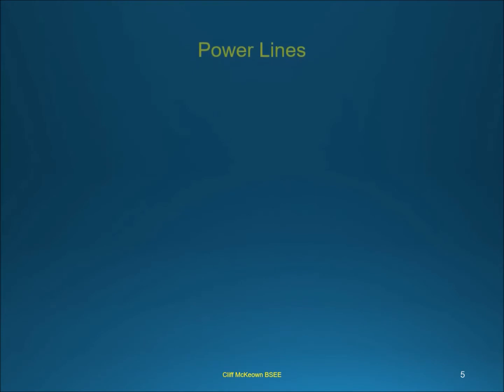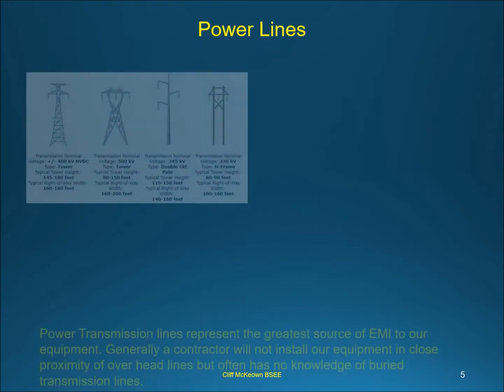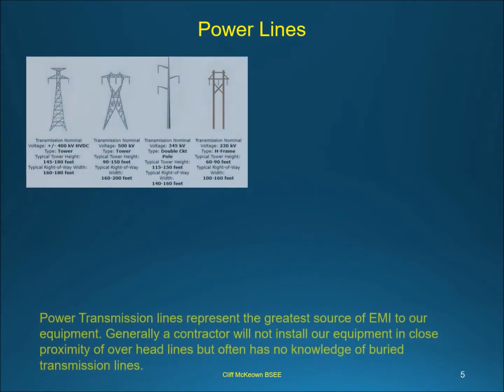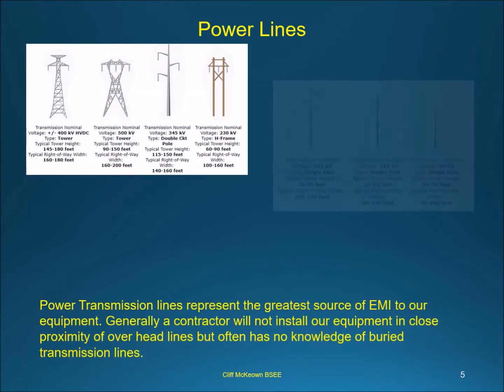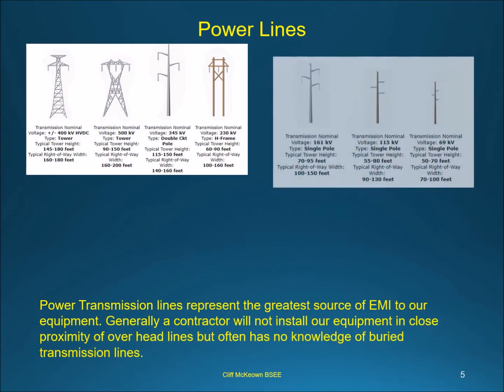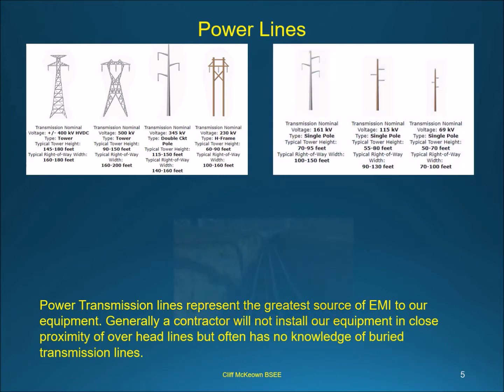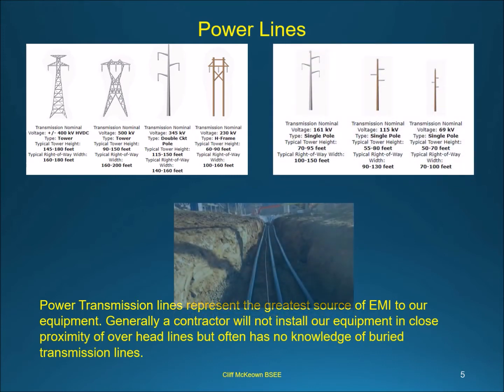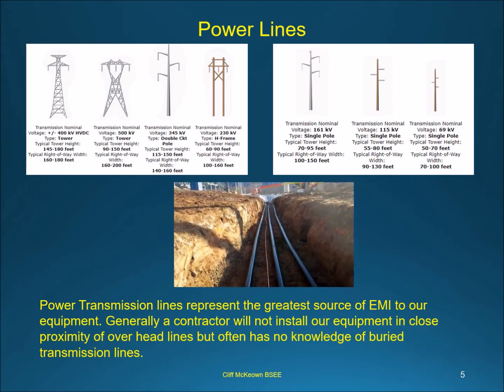Power transmission lines represent the greatest source of EMI to our equipment. Generally a contractor will not install our equipment in close proximity to overhead lines but often has no knowledge of buried transmission lines. Careful consideration should be taken when installing electromagnetic flow meters in close proximity to power lines. Maximizing the distance between the power lines and the meter is the best method of preventing EMI.